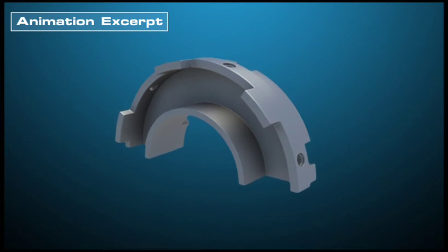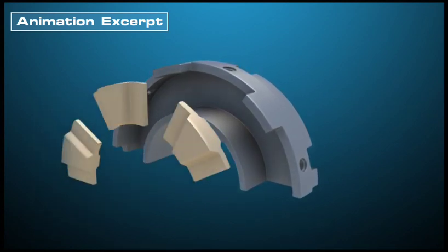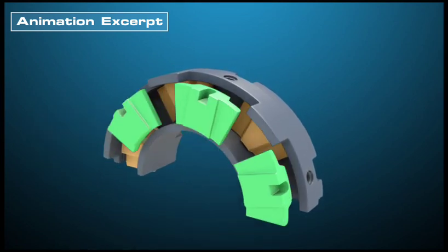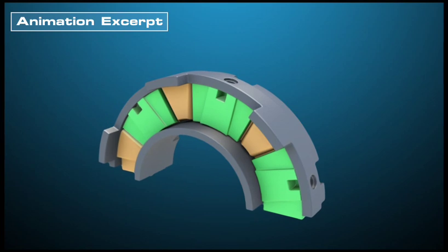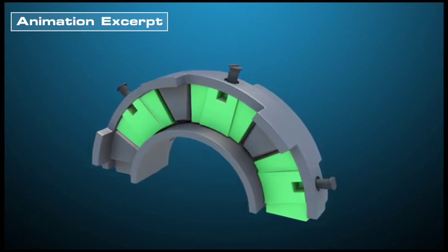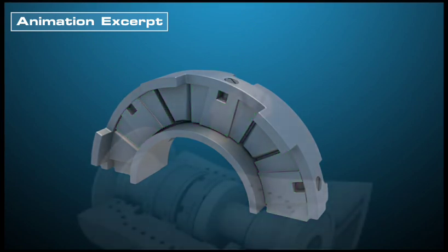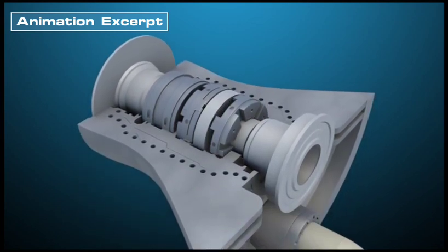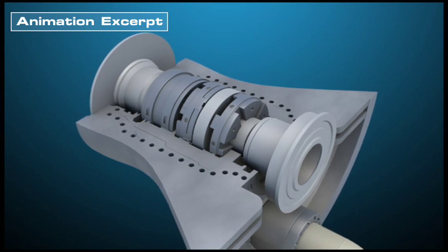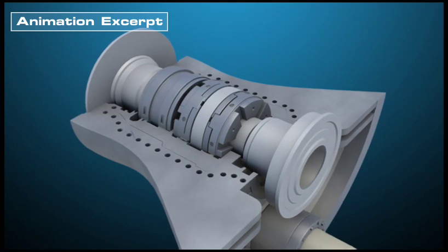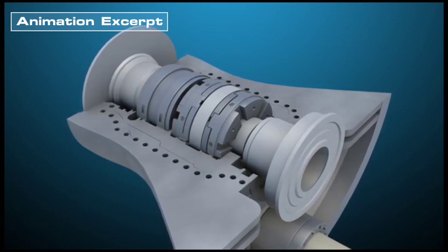To assemble the bearing, the inner leveling plates are placed in position first. Then the upper level plates rest between the inner leveling plates. Plate set screws will keep the upper leveling plates in position to ease assembly. The lower halves are placed on the shaft, and with the base ring in position, the thrust pads are slid into position. This assembled section is now rolled into position.